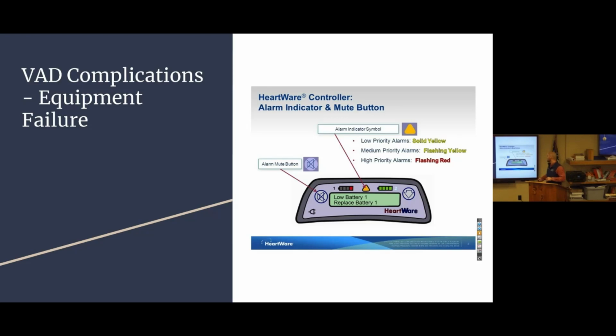The alarm systems for most of these are prioritized - you can have a low priority alarm, a medium priority alarm, and high priority alarms. We'll talk more about alarms in a bit, but there's a really good resource called the Mechanical Circulatory Support Emergency Guide. It's put out by a group of clinicians who deal with mechanical circulatory support, and it has a quick guide on how to put the battery back in or how to connect the driveline back into the controller.